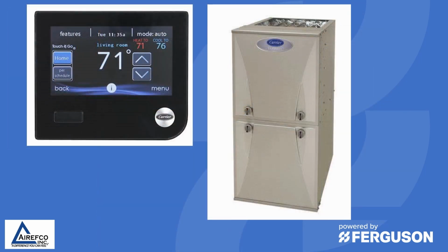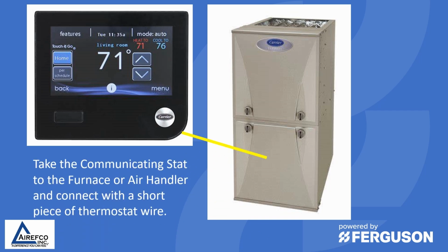If you still cannot establish communication between the user interface and the gas furnace or air handler, one of the tricks that we do is to take the user interface and go to the furnace or fan coil and connect it with a short piece of thermostat wire. If it finds the furnace or the fan coil on this short piece of thermostat wire, then you know that you have a problem in the wiring between the thermostat and the fan coil or furnace.